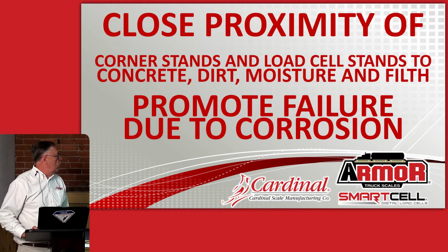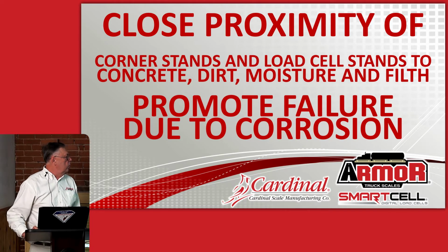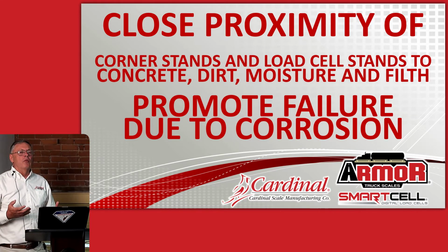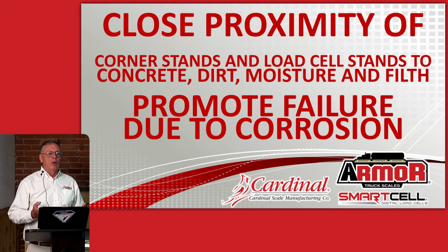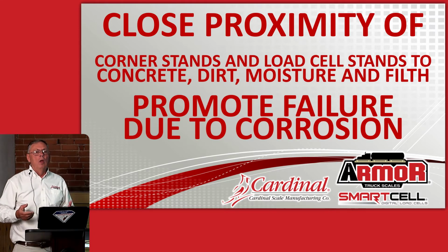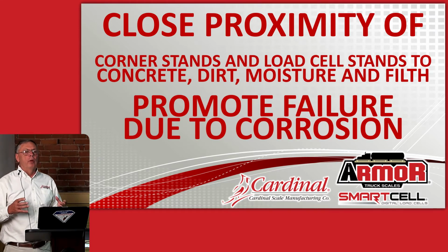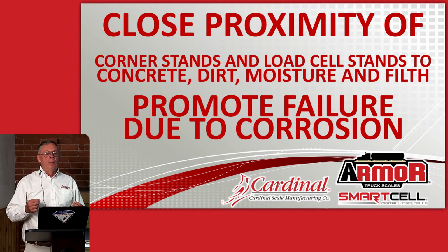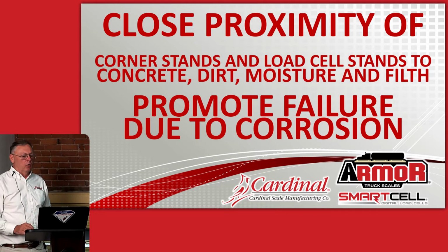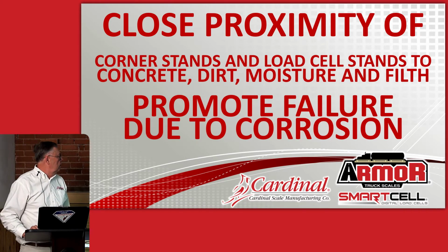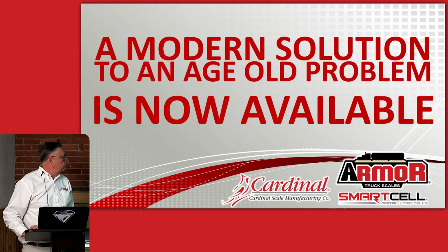Close proximity of the corner stands of the load cells to the concrete, dirt, moisture, you'll have the corner stands rusting out over years, and the whole side of the scale will collapse. A lot of times the corner stands are just built out of like 8-inch channel iron that's only 3/16 of an inch thick, so they're susceptible to rusting out.